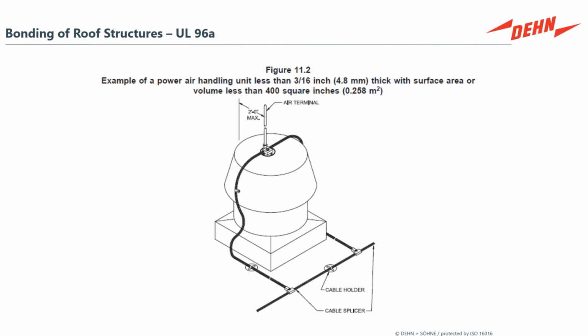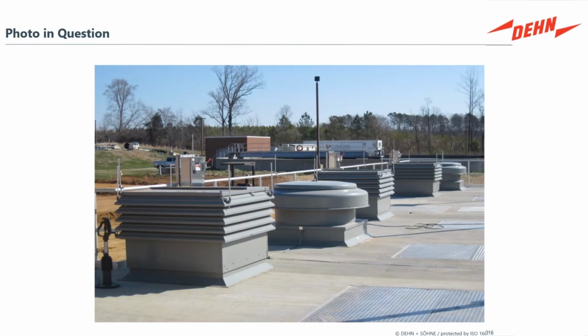A lot of times visually it looks a lot like this. You'll see it a lot where the air terminal is attached and bonded to metal framework and fan vents, maybe things like air chillers that are up on the roof of a structure. And so you'll see things like these air terminals on the structure bonded to the framework. And this might be over the top. You can picture this in a charging station type environment where it's around the buildings adjacent to the charge station, the hotels, the convenience stores, the things where a charging station is going to be. And you'll notice that the lightning is subject to be injected directly into the frame. And then some of that lightning current finds its way directly into the electrical systems within a structure.